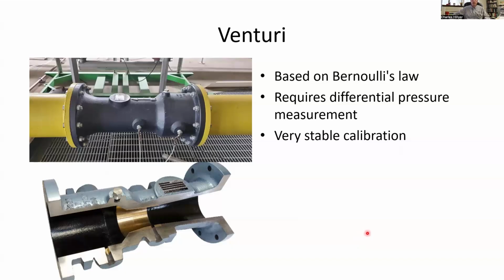Now, this meter operates by using something called Bernoulli's law, and it basically measures a pressure difference. So there's a pressure tap right there, and there's a pressure tap right there. And it gives you a very reliable measurement of the flow rate going through that meter by measuring a difference in pressure. Now, that means you have to have a pressure transducer, and those pressure transducers have to be calibrated. But that's much easier than trying to get this giant flow meter calibrated because it's quite heavy and it costs a lot to have it shipped around. So Venturi flow meters are available in agricultural settings. They don't get used very often, but they are very stable and they are very reliable, but you do need a pressure measurement.